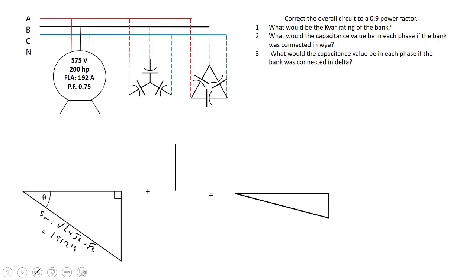We know that the power factor of this motor is also given, so that is a power factor of 0.75. I can figure out the power of this motor by multiplying my apparent power by 0.75. So the true power of this motor is 143,414 watts.